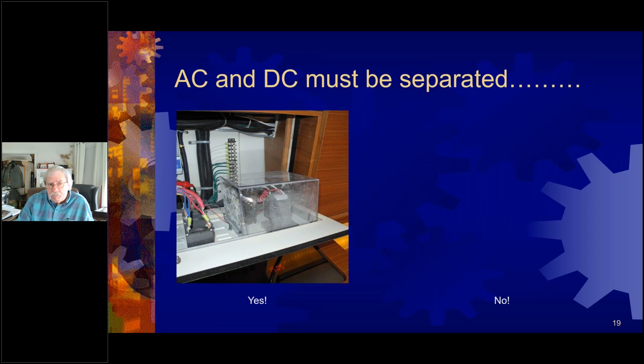We have not specified limitations on material. That one happens to be made out of Lexan. I've seen some made out of wood. There are multiple ways you can comply with the standard. This panel board, we've got DC on the top, AC on the bottom. There's no separation. This is a non-compliant installation at this point in history.